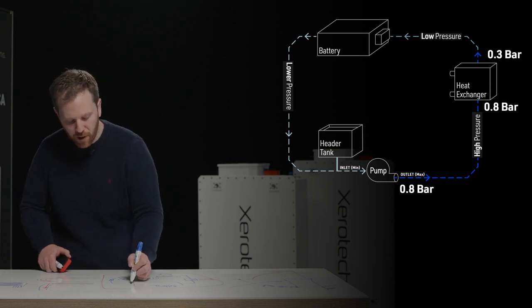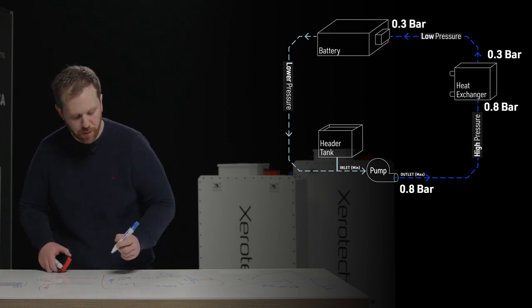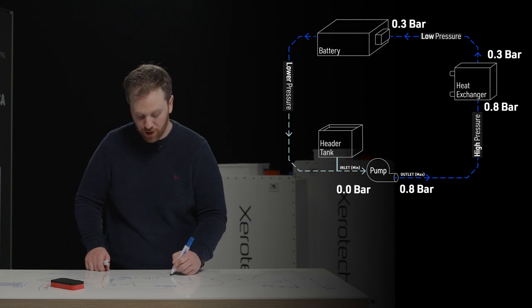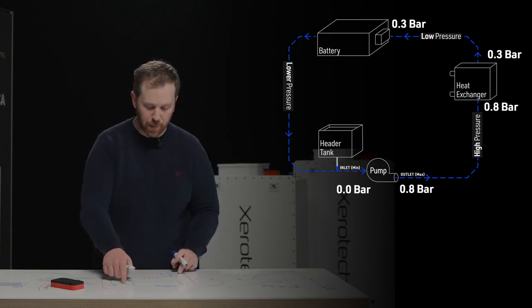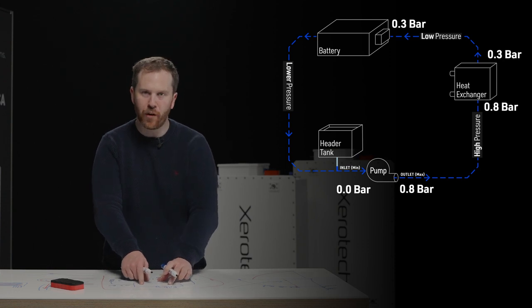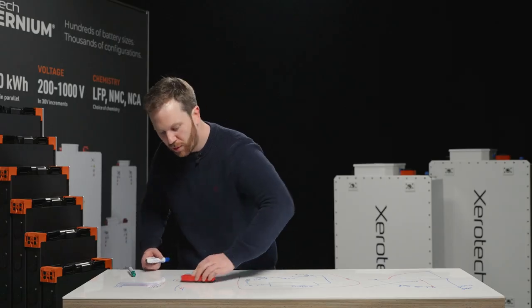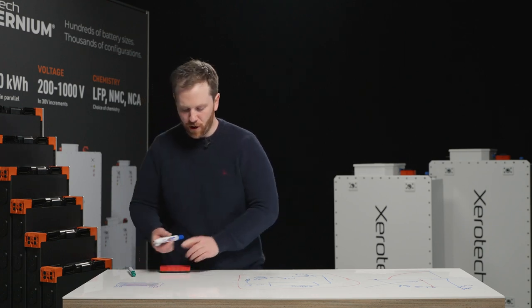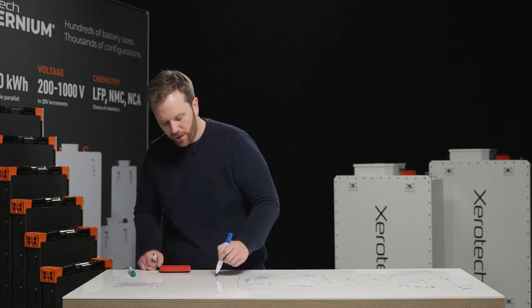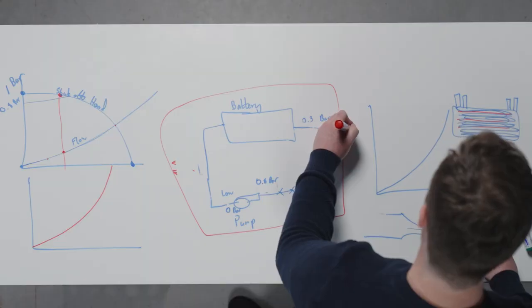And then as it reaches the battery pack, it's now going in at 0.3 bar. Because the outlet of the battery is basically on the suction side of the pump, the pressure here will be effectively 0. So this small pressure difference can develop a large flow rate across a Xerotech battery. That's very important, and you'll see that in all of the Xerotech battery data sheets, that we show the pressure characteristic curve for it. And what that will show is to develop a certain flow rate, if you want more flow, the pressure drop will be on the other axis, the y-axis.